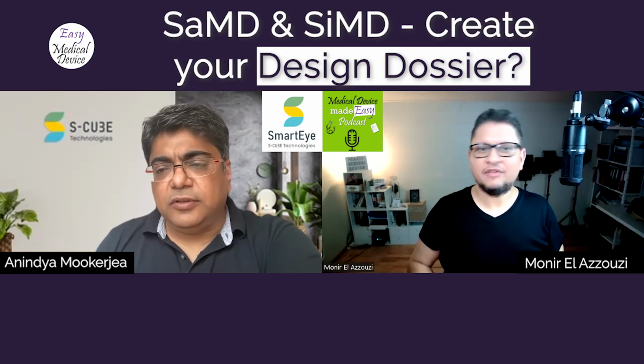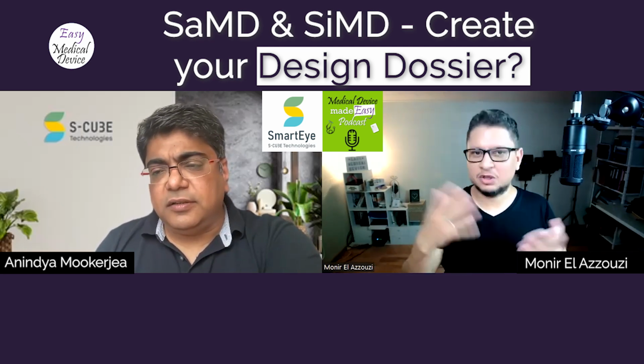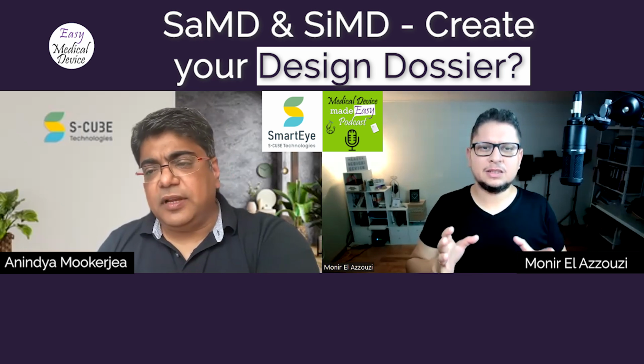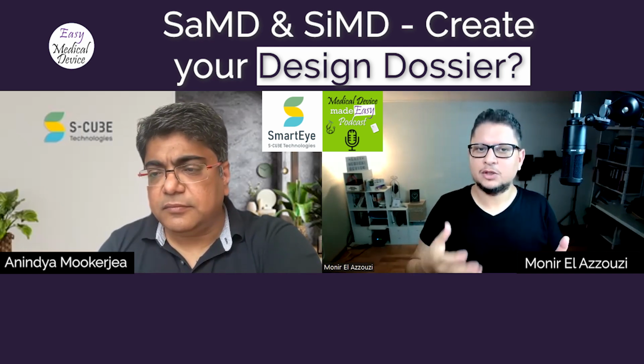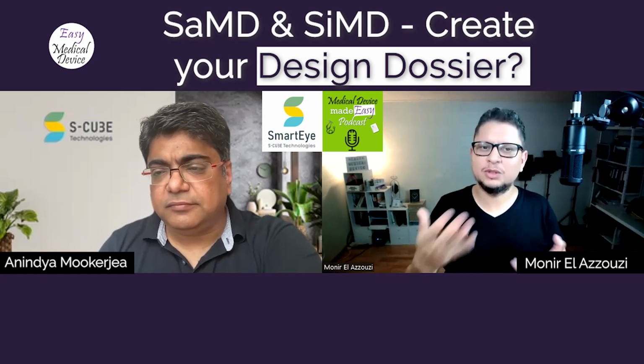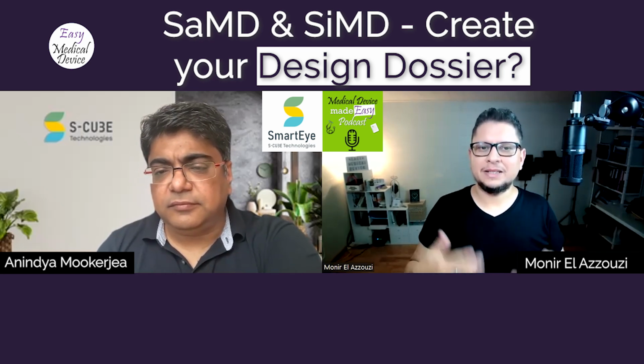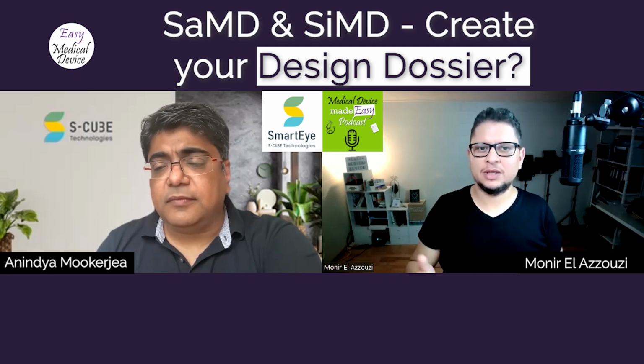So for you, there is no need to think anymore, because when you go to the 62304, first it asks you what is the classification of your device, class A, B, C. Then when you go inside, it tells you this chapter is for class A, B, C, this chapter is for class B and C, this chapter is for class C also. So mainly the idea is that everything is now directly provided to you in SmartEye. There is no need to think, should I do this, should I do that, because everything is there. It's really something you are developing to help companies make it easier from start to end.